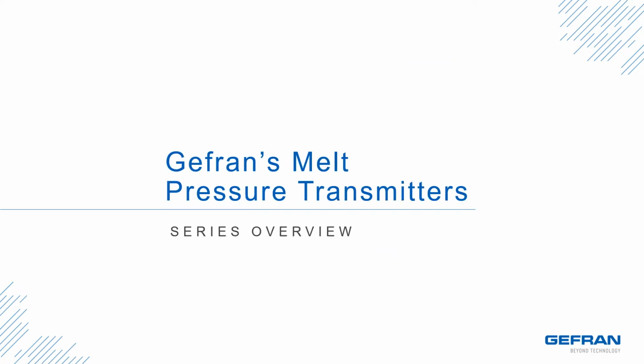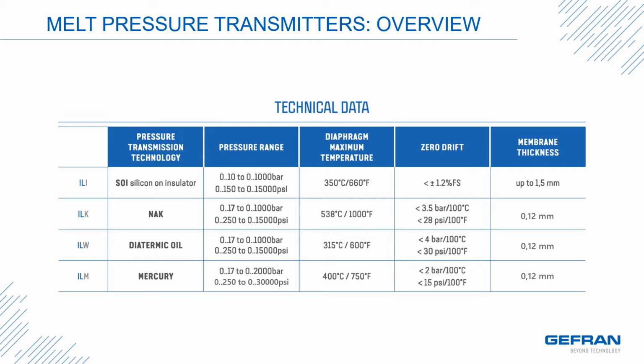Now I'll go into a little more detail about all of the models in the series. Gefran offers the IO-Link output on all four of our sensing technologies in melt pressure sensors. The ILI is our impact sensor, a fluid-free design with a process temperature maximum of 660 degrees Fahrenheit. The ILK, our fluid-filled sodium-potassium or NaK-filled sensor with a process maximum temperature of 1000 degrees Fahrenheit based on proper diaphragm selection. The ILW, FDA-approved oil-filled sensor with maximum process temperature up to 600 degrees Fahrenheit. And the ILM, our mercury-filled sensor with maximum process temperature up to 750 degrees Fahrenheit.